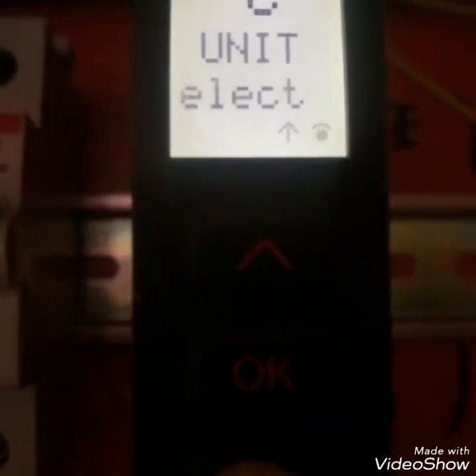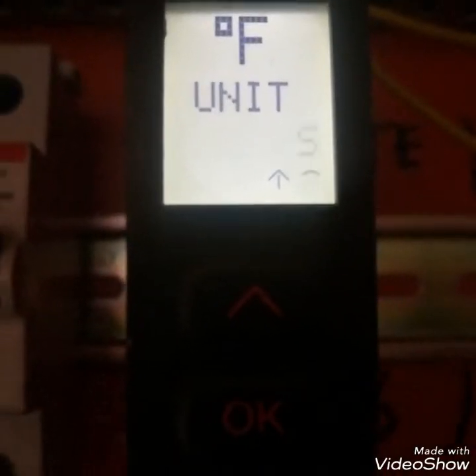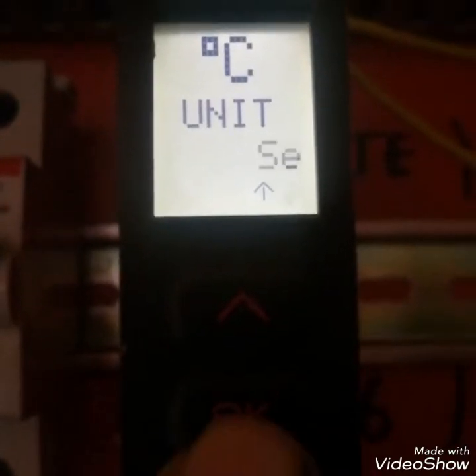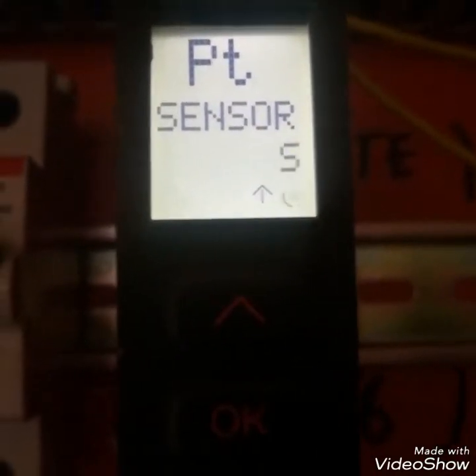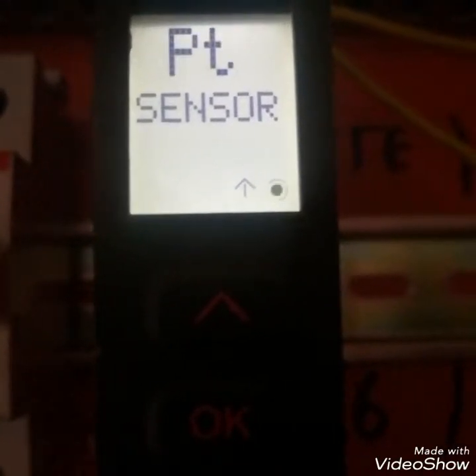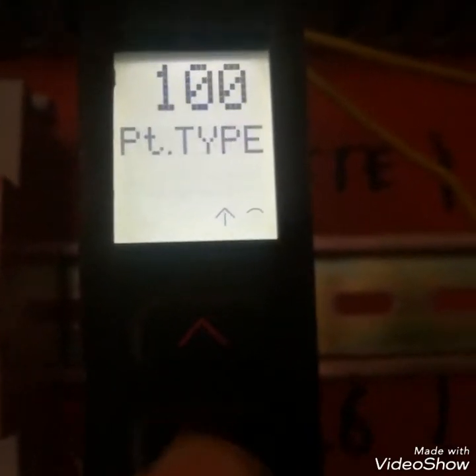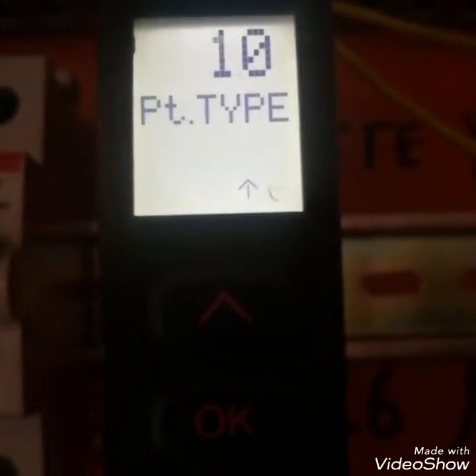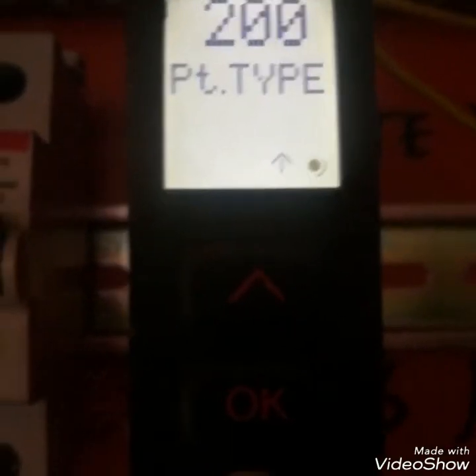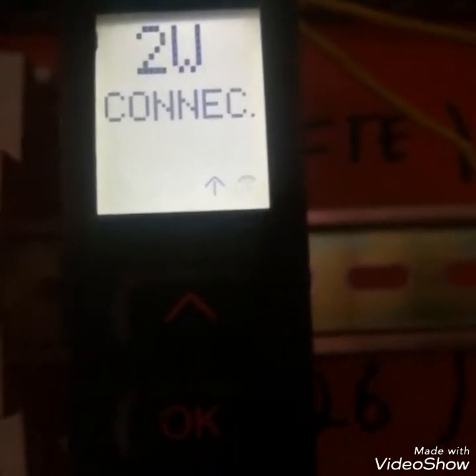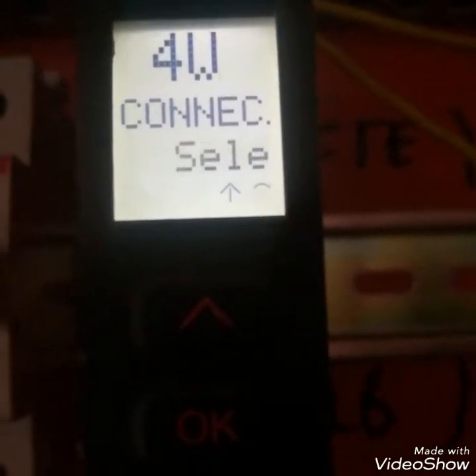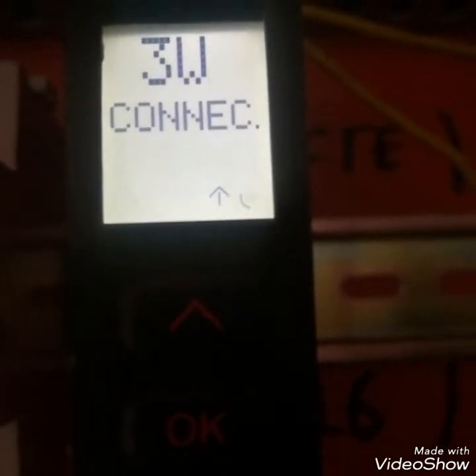Unit may be centigrade or Fahrenheit. We are using centigrade. What is the input sensor? Platinum, nickel, thermocouple. We are using platinum PT. What is the type of PT? PT 100, 50, 20, 10, 1000, 500, 400, 200, but we are using PT 100. What is the connection, 2 wire, 3 wire or 4 wire? Our connections are 3 wire, so I will configure 3 wire.